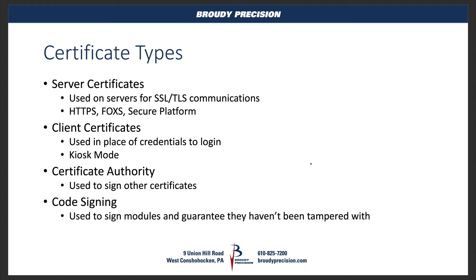Our last type of certificate is a code signing certificate. This is probably not something you would ever create yourself unless you're doing development for Niagara, but you'll probably run into them as we get into newer versions of Niagara. A developer would sign a module, and that signed module would verify that the contents have not been modified or tampered with — so a third-party entity hasn't gone in and messed with code without you knowing. This would tell you if a module's been modified since it left the developer's hands. In later versions of Niagara, modules will be required to have a verified signature certificate or Niagara won't run them at all.